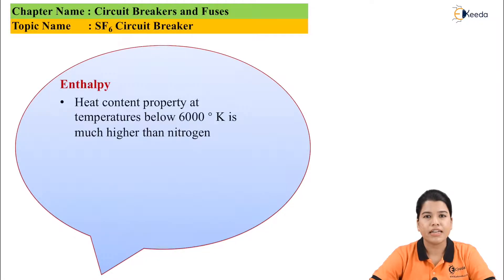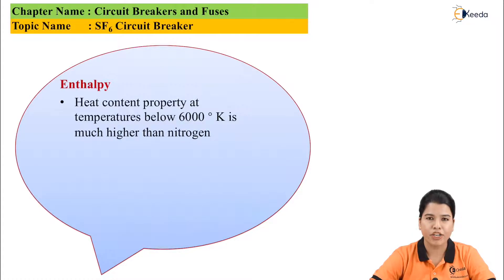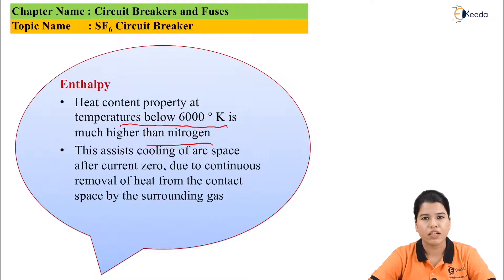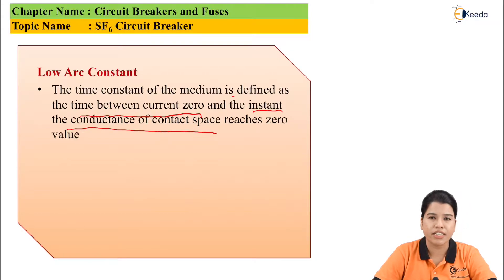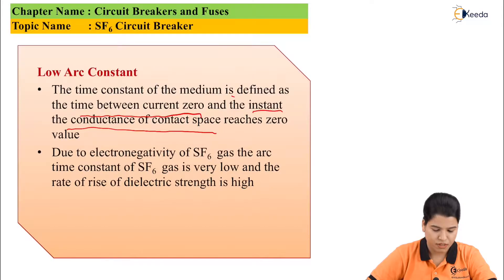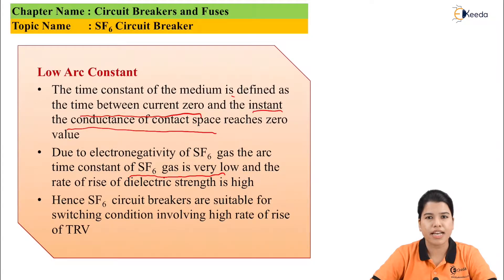The next property is enthalpy. The heat content of SF6 gas at temperatures below 6000 degrees Kelvin is much higher as compared to nitrogen. This property assists in the removal of heat due to constant cooling provided by fresh SF6 gas. The next property is low arc time constant, defined as the time between current zero and the instant the conductance of the contact space reaches zero. Due to the electronegativity of SF6 gas, its arc time constant is very low compared to the rate of rise of restriking voltage, making SF6 gas very useful at high values of TRV — transient recovery voltage.